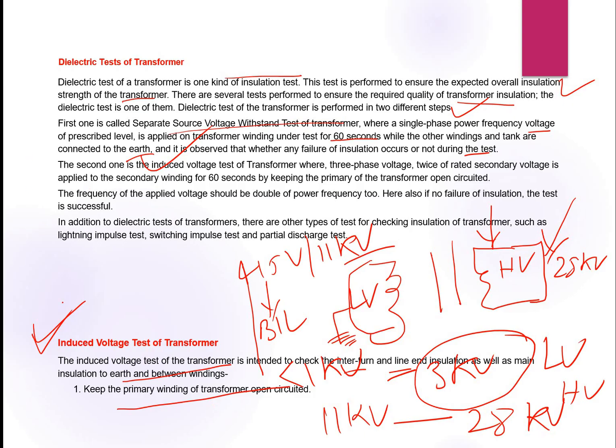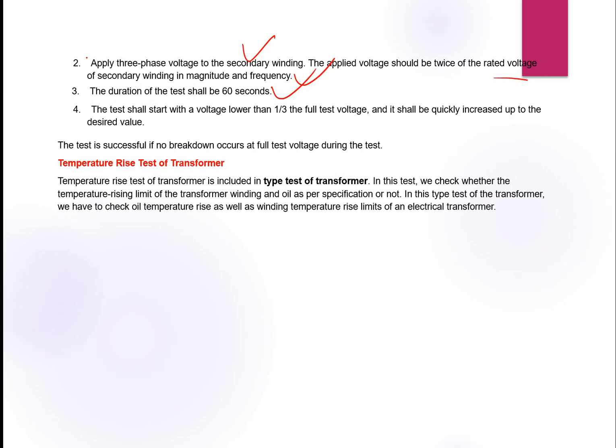So if you want details on the induced voltage test of transformer, the first step is to keep the primary winding of the transformer open circuit and apply three phase voltage to the secondary winding. Applied voltage should be twice the rated voltage of the secondary winding in magnitude and frequency, and duration of the test is 60 seconds, initially one third of the voltage and then increased up to the desired voltage. This test is successful if no breakdown occurs at full test voltage during the test.